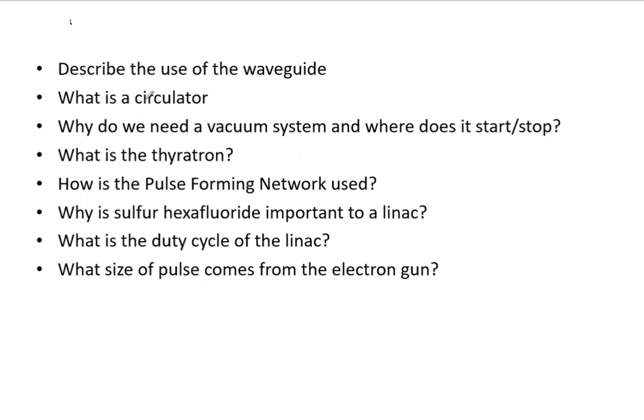So to begin, the use of the waveguide. This confines the microwaves by reflecting them off walls, kind of like water in a hose that is flowing through it. So it's pressurized with freon or SF6 which prevents electrical breakdown.